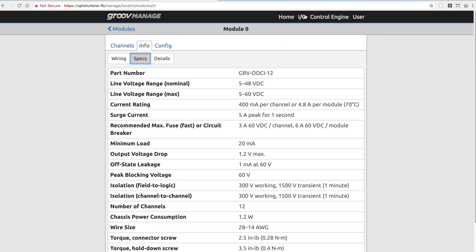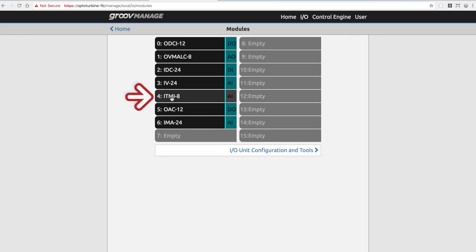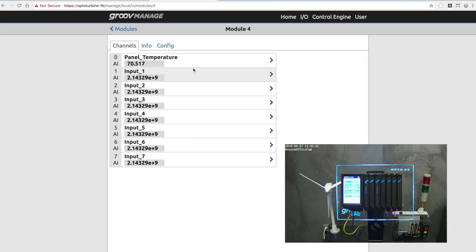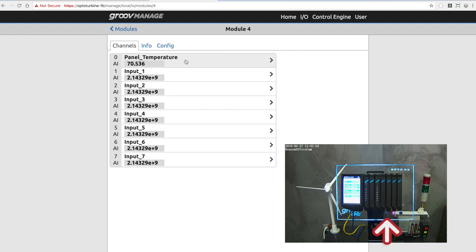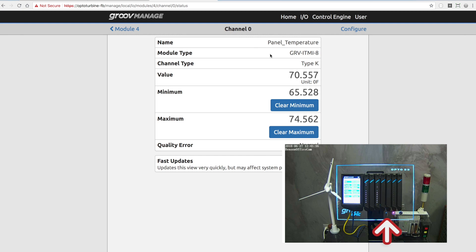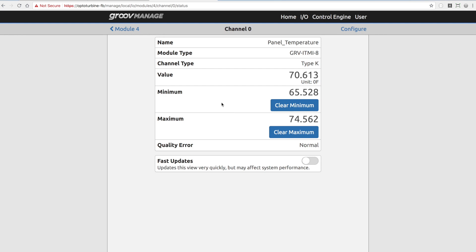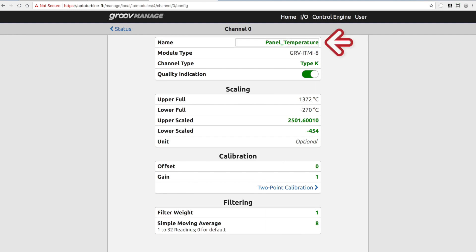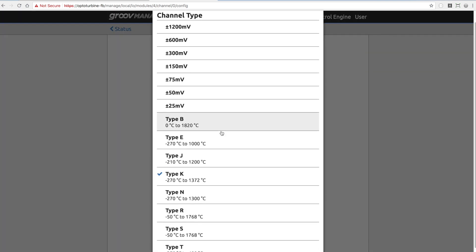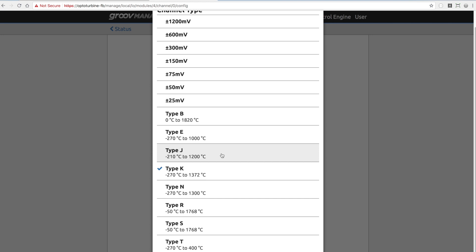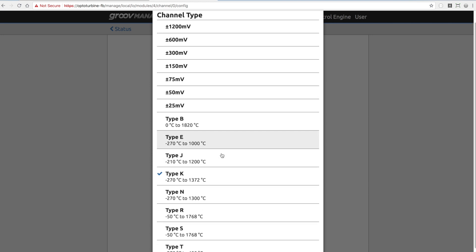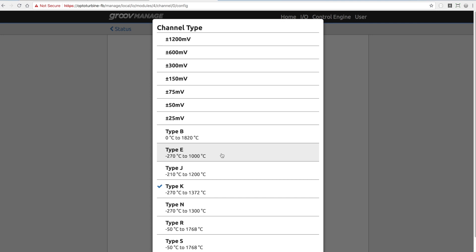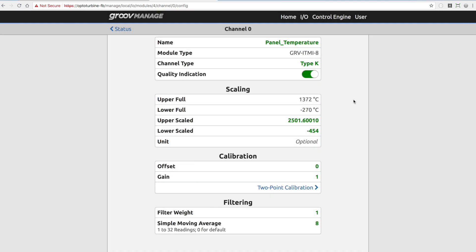Going back to I/O, let's take a look at another channel — in this case, the panel temperature, which is a thermocouple wired onto the front of the panel. It's currently at 70 degrees. I can see its name, module type, values, minimum and maximum, and so on. This is an example of some of the smarts in these modules — if I go to configure the module, I can change the channel type. If I decide to move to a type J thermocouple, I simply select it and apply the changes. This particular module provides an array of different thermocouple types and millivolt types, all right there at your disposal.